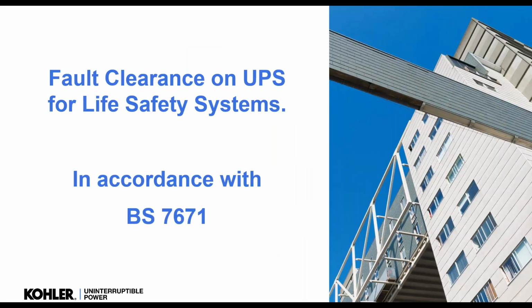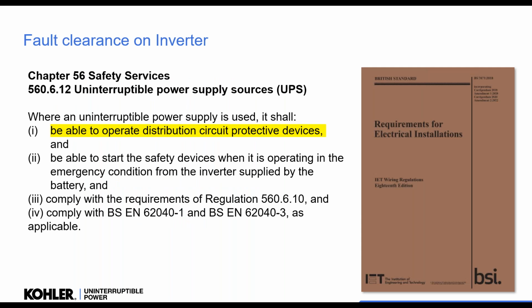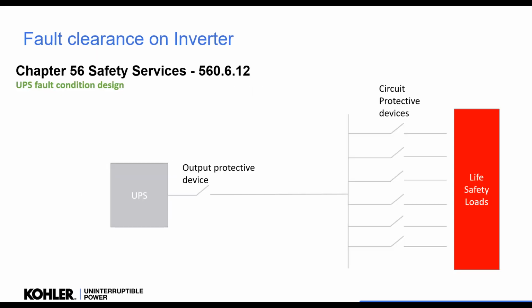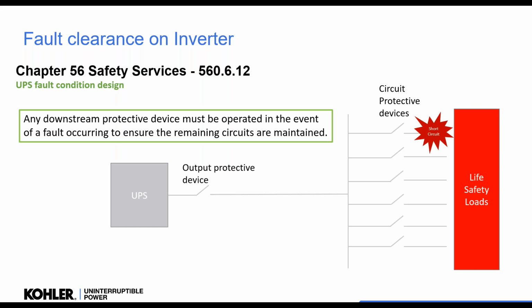Now, hopefully standards get better, because we do have changeovers in the UPS that could be used at some point. So we're putting a UPS in, and now we have to consider fault clearance on the UPS in accordance with 7671. This is hopefully familiar to those who work on critical medical areas, because it is the same thing. Where a UPS is used, we must be able to operate the distribution circuit protective devices downstream. So we've got the UPS feed and output board with a number of life safety loads, and if we have a fault downstream on a final circuit, we must be able to operate the actual protective device to make sure that all the other loads continue to operate. We don't want the UPS turning off, because that would turn off all the life safety loads.